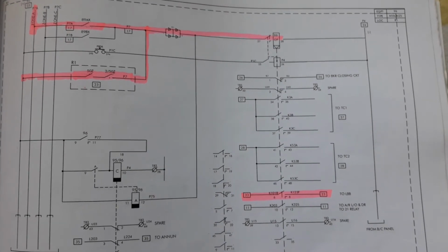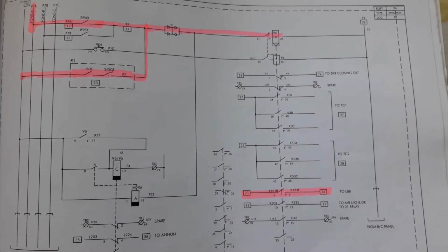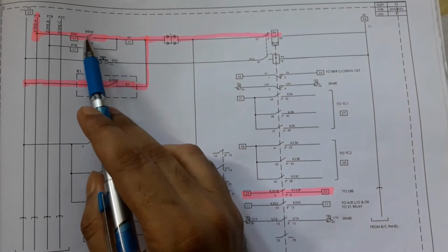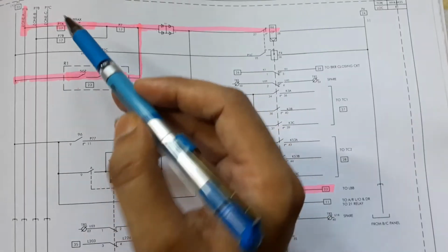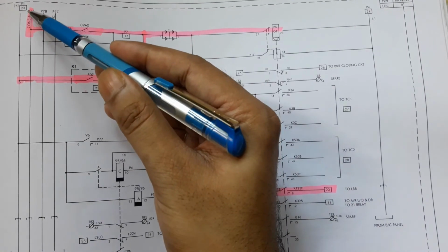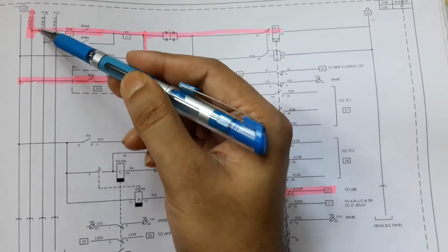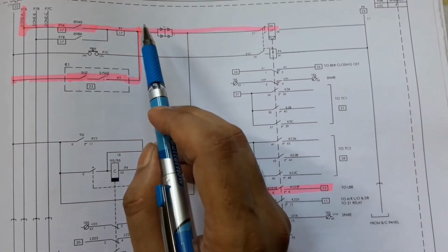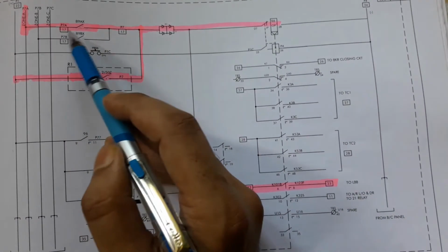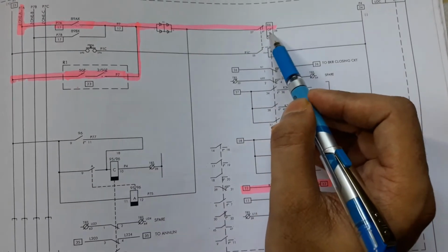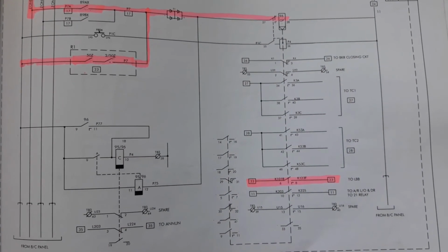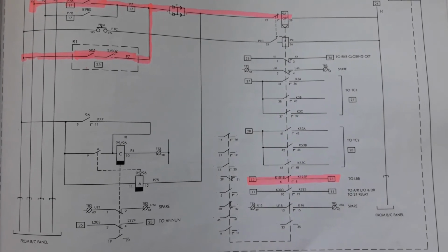But if any bay is not connected with main bus 1, then the isolator contact will be in break condition, and in spite of energization of this P7A bus wire, the 96 relay connected with that bay which is not connected with bus 1 will not operate, and the circuit breaker of that corresponding bay will not trip.